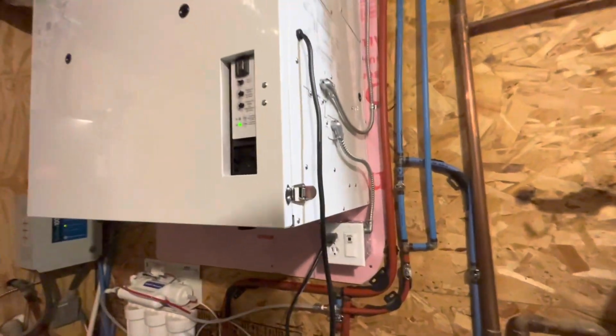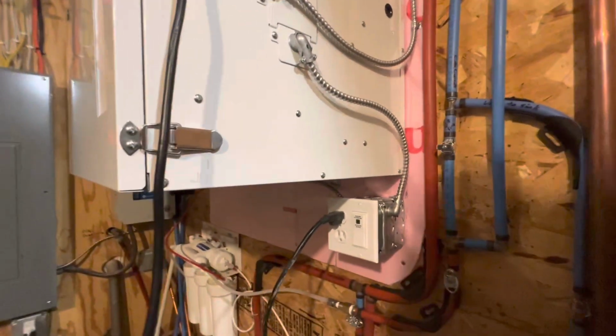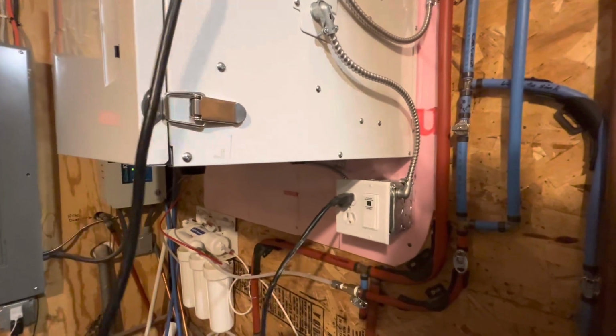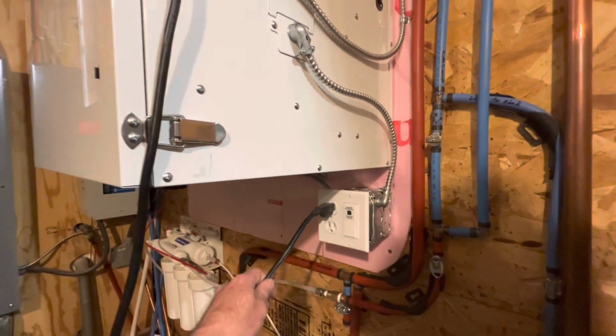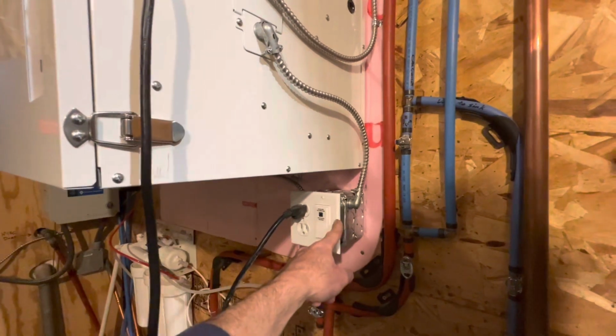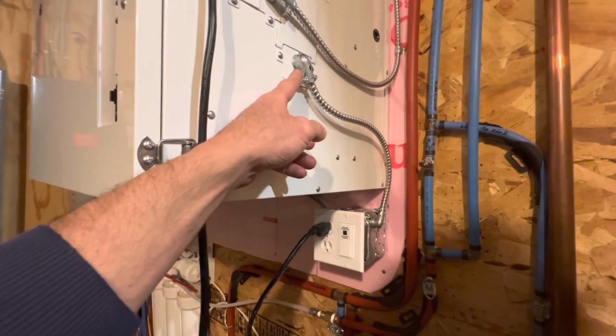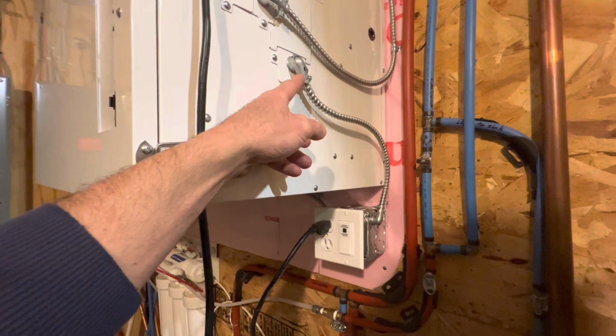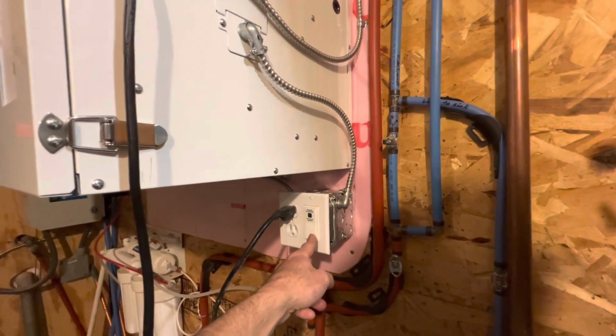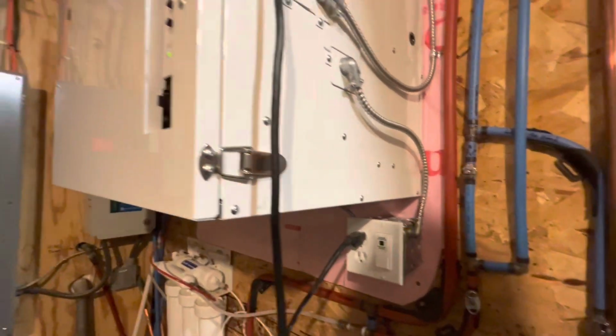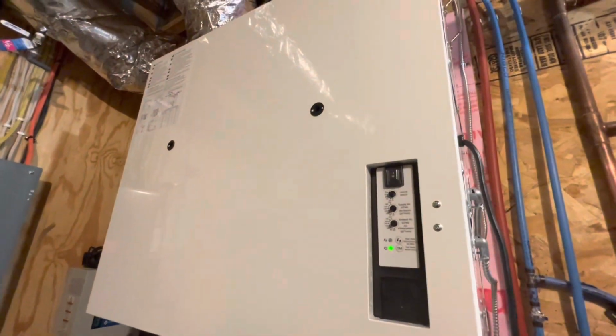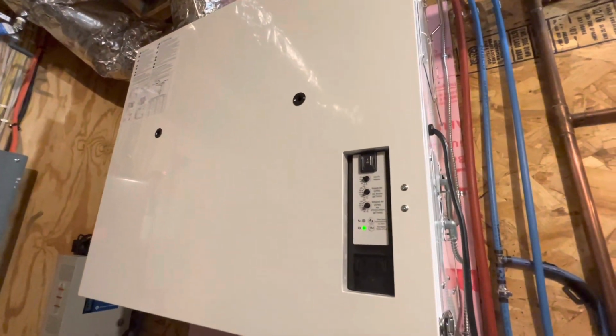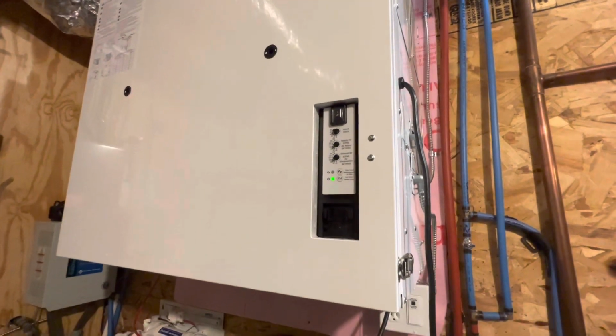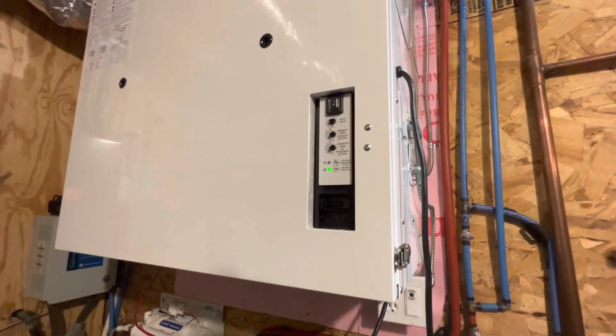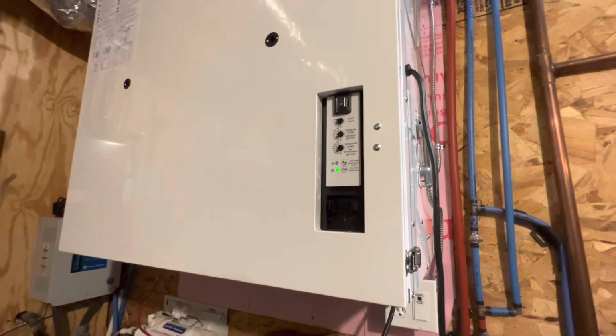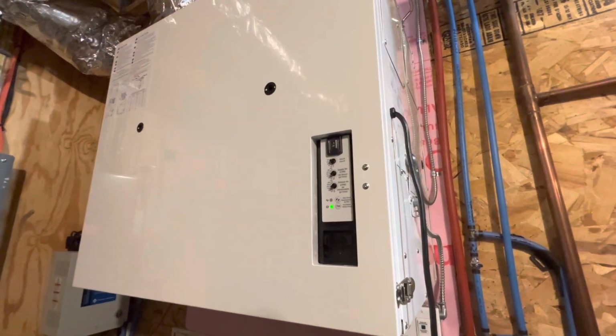For the power install, you need to do a normal wall plug. Obviously that's what this is. That's the power supply. The wall switch gets wired in. That's a recommended install. You want to shut off the wall switch before you do maintenance. That gives the internal dampers a chance to shut before you open the door. The door has a safety switch that shuts it off when you open it, so the dampers don't have time to drive closed.